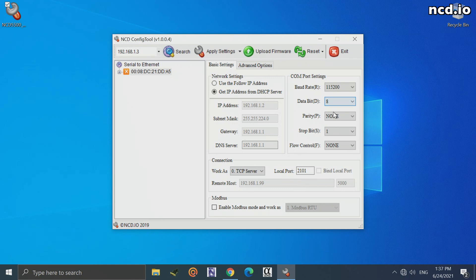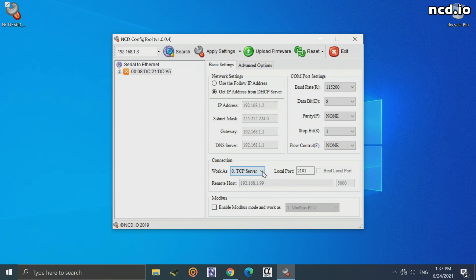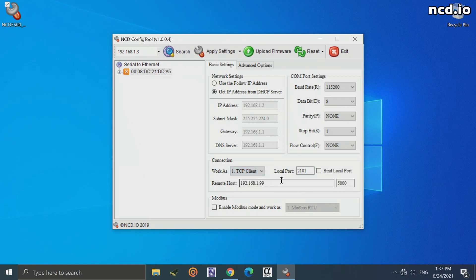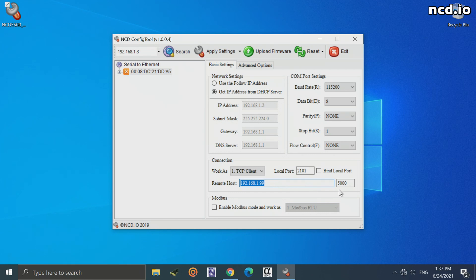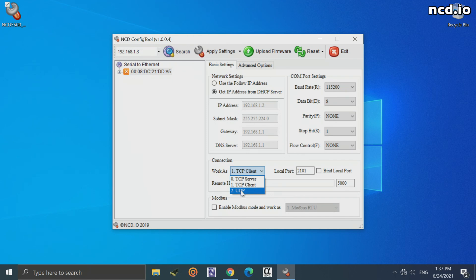I don't really ever recommend that you change these COM port settings. This will break the communication between the Ethernet module and the wireless module inside the Ethernet modem. Here we have the connection. Right now, we have it working as a TCP server. As I said earlier, in this configuration, the Ethernet modem is the server and your software is the client. If you want to change that, you can make this device the TCP client, and you can tell it a remote IP address and port to connect to. This would be the IP address of the computer that's running your software, and this would be the port that your software is listening on. You can also change it to UDP so that you can get data from the device via UDP.